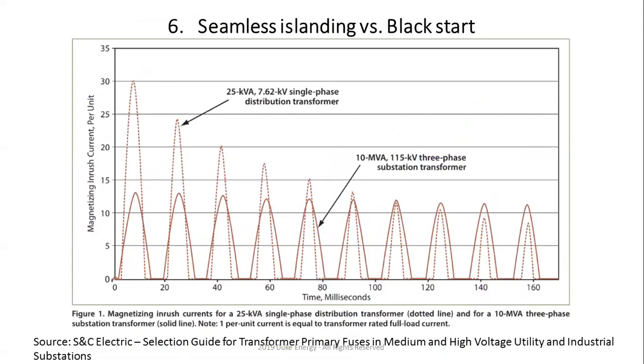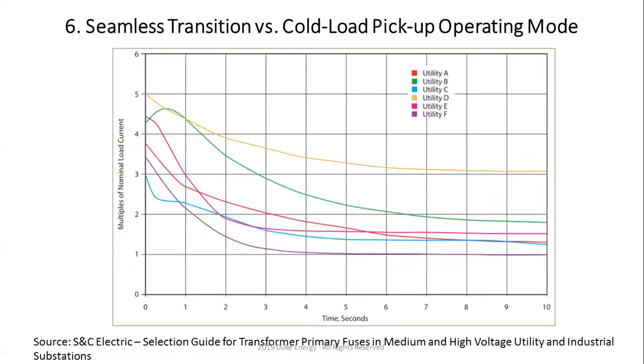And what I told you a long time ago, I think on some of the first slides, you can see the inrush current. This is from the S&C Electric Selection Guide for transformer primary fuses. You can see the per unit inrush current for different size transformers, right, as a function of time in milliseconds. So probably one of the most challenging parts is how do you energize the transformer? In order to do that, you have to have these curves and figure out how to minimize the inrush, because most of the time I don't know if your generator is going to be running. And also you have to understand when you do the black start versus seamless islanding, there's a major design difference, right? Because when you do black start, you follow one design methodology versus seamless islanding with respect to the size, right?